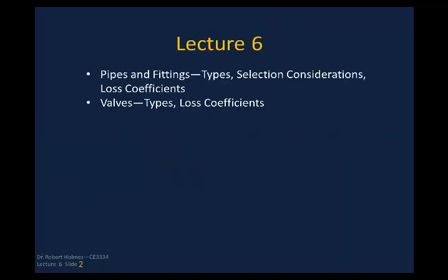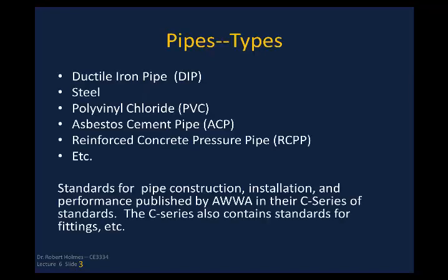This slide shows what we're going to cover. As I mentioned earlier in lectures three and four, the largest outlay of capital in any kind of design is going to be the pipe, so selecting the right pipe is important. There are various types: ductile iron pipe (DIP), steel pipe, polyvinyl chloride (PVC), asbestos cement pipe (ACP), and reinforced concrete pressure pipes (RCPP). The standards for these are contained in the American Water Works Association C-series of standards.